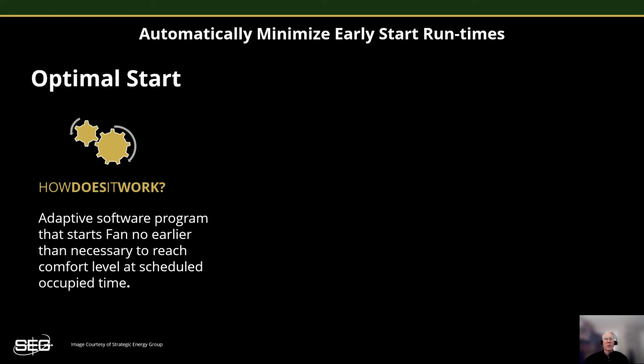So when we discuss startup times for HVAC equipment, we need to take into account the fact that most buildings will need some extra time to get the building spaces warmed up or cooled down to their occupied set point each morning. Typically, your HVAC equipment needs to start a bit earlier than the occupied time. Remember, the occupied time is the time that you've identified as being when the majority of occupants begin to arrive. And it's important to note here there's a distinct difference between the time that the HVAC equipment needs to start in order to get the spaces to set point and the time that's been identified as when occupancy begins. The equipment start time will almost always be before the occupancy time, and the amount of time between the two is called the early start time.